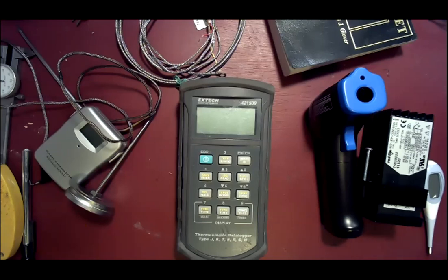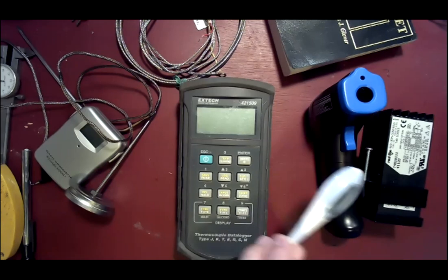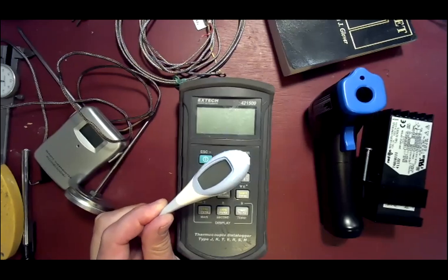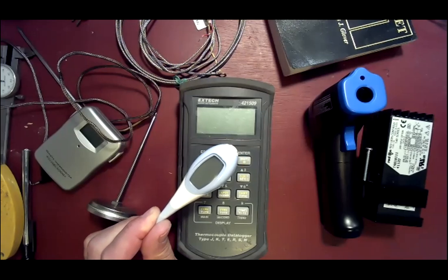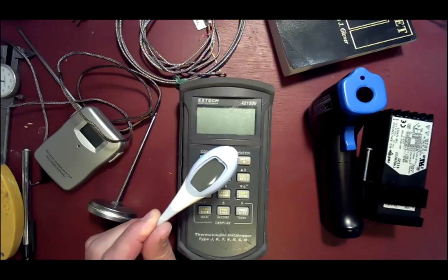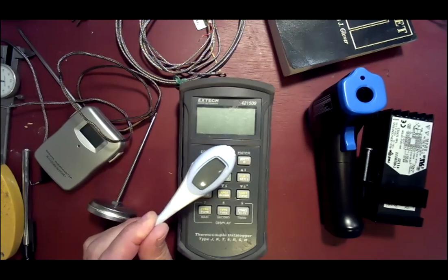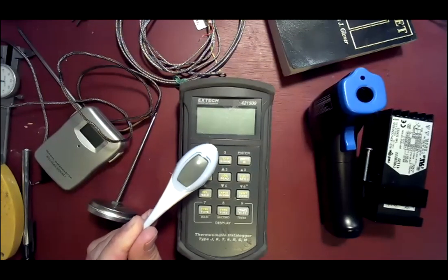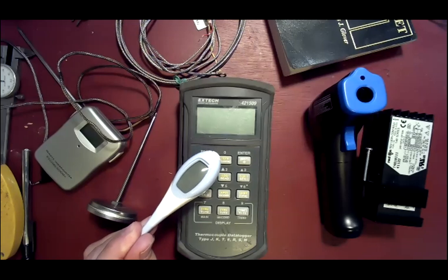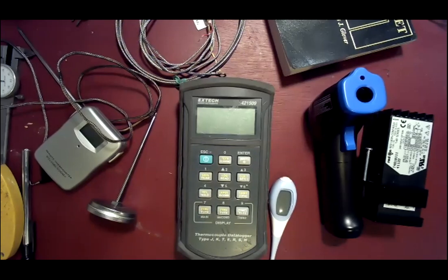Secondly, it was given time for the mass of the probe to reach stability. So the mass warmed up and the temperature reached a stable point. Number three, it had really good contact with the object it was measuring, which in this case is my human body, and it was stuck under the tongue and pressed really hard against it. So full immersion, excellent contact, and given the time to reach the temperature of my human body. Those are three very, very important ideas about temperature measurement.